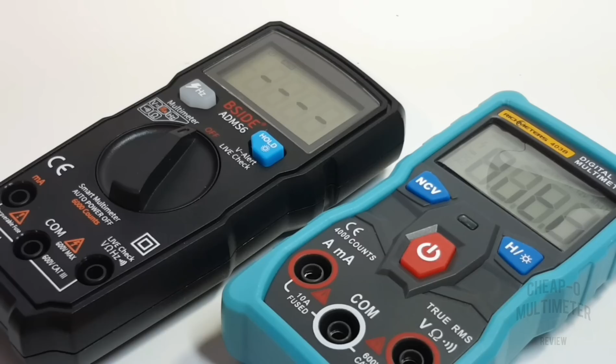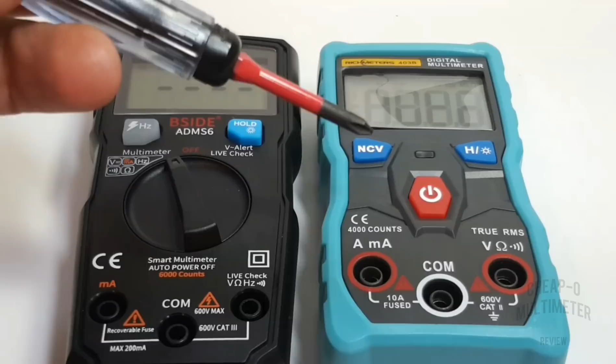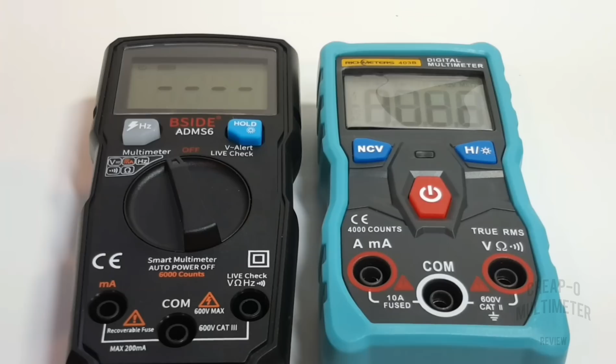Size-wise, it's quite similar to another auto-range we looked at earlier, the 403B. Put them side by side, you can see it is maybe just a tad, about half an inch, a couple centimeters longer than the Richmeters, but pretty well neck and neck in terms of size and weight. In contrast to the Richmeters, you can see the BSIDE, even though it is automatic, still has that old school selector switch, compared to the Richmeters, which have done away with the selector entirely and are strictly push button.